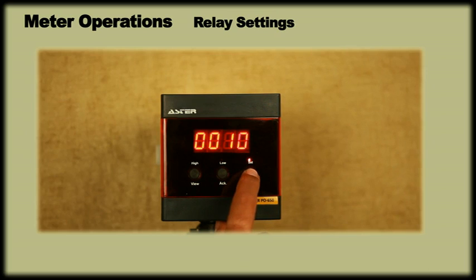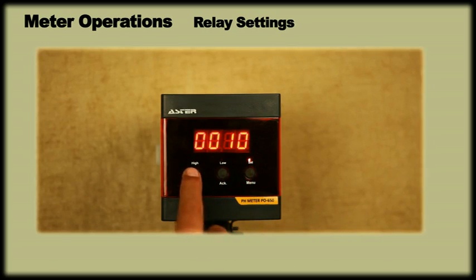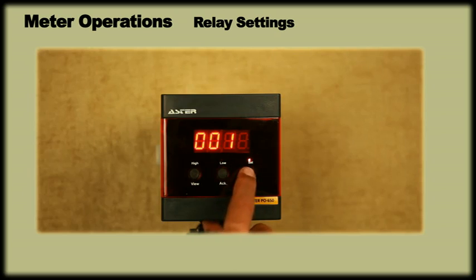On pressing menu, it will show a previously set hysteresis value. Using ACK key and view keys, we can set the required hysteresis value. Let us set hysteresis value at 10% and press menu to enter.